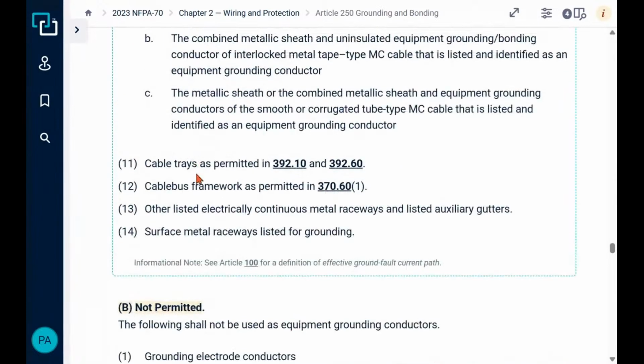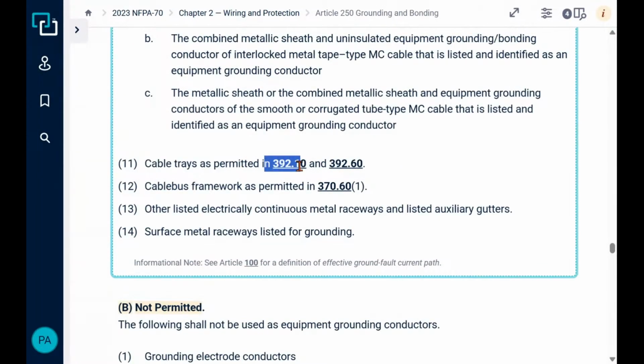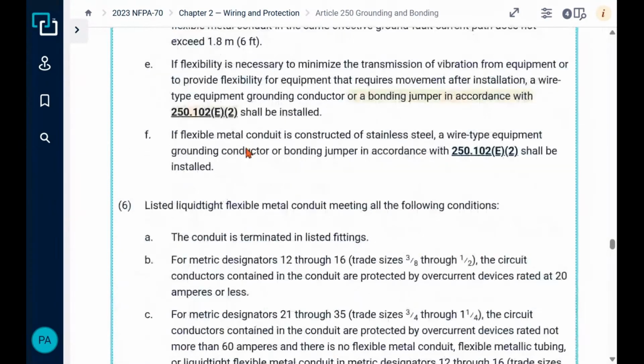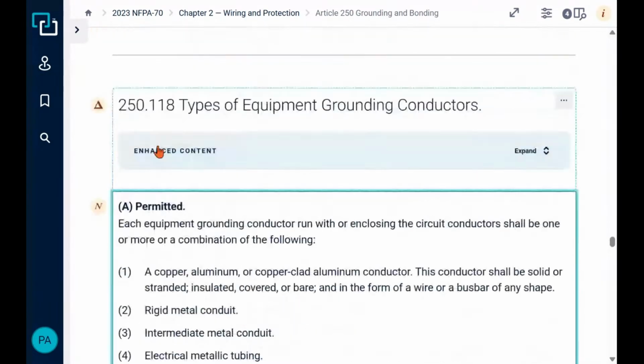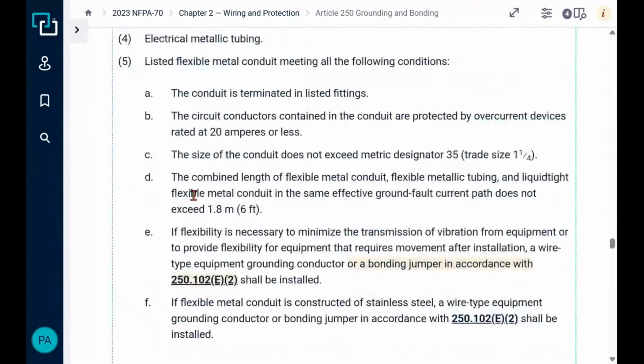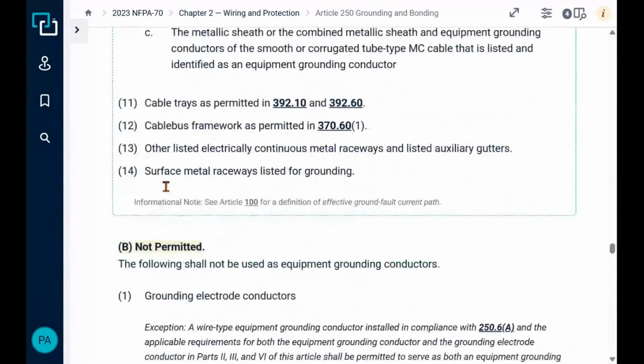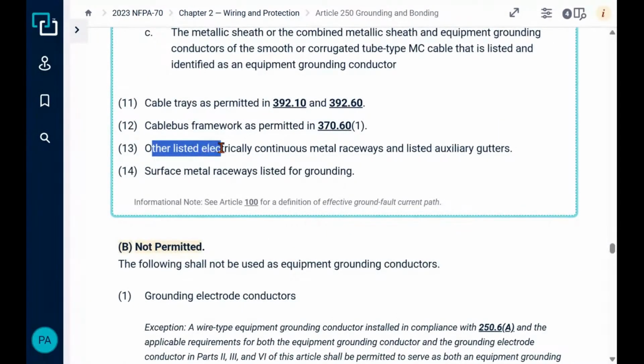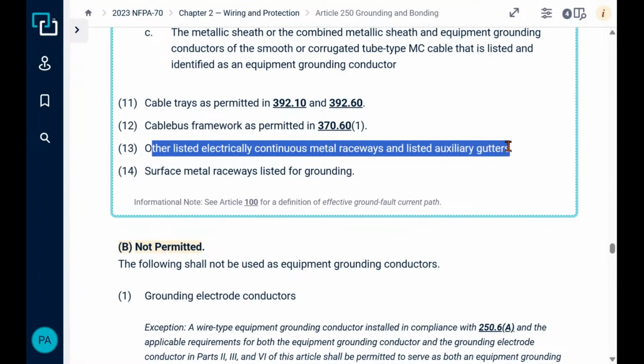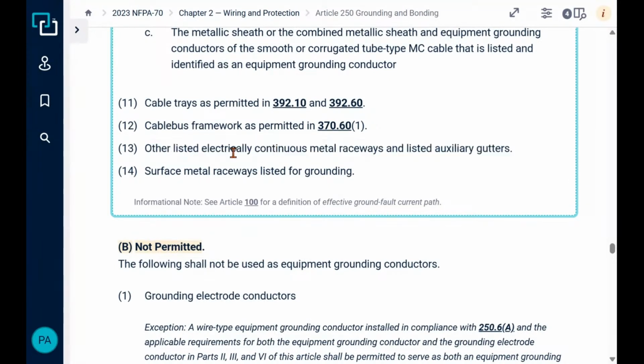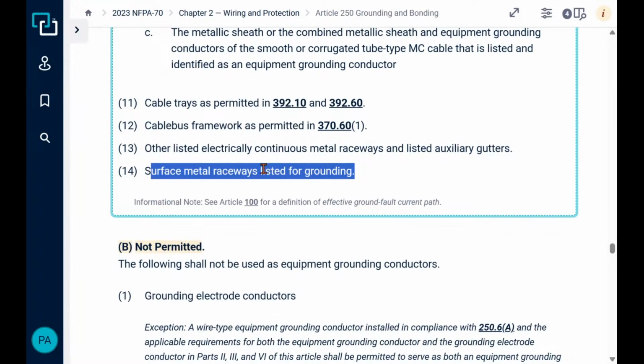So, well, there's the cable tray one right here. Cable trays are permitted, okay? And again, this is where it's talking about permitted for use as equipment grounding conductor. So we qualify that. Let's see here. Here you go. Other listed electrically continuous metal raceways and listed auxiliary gutters. Okay. So other listed. So listed for use. Okay. We also see surface metal raceways listed for grounding. Okay. All that type of stuff.